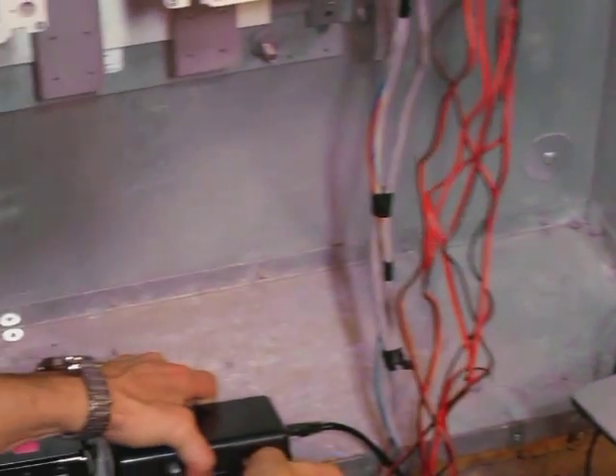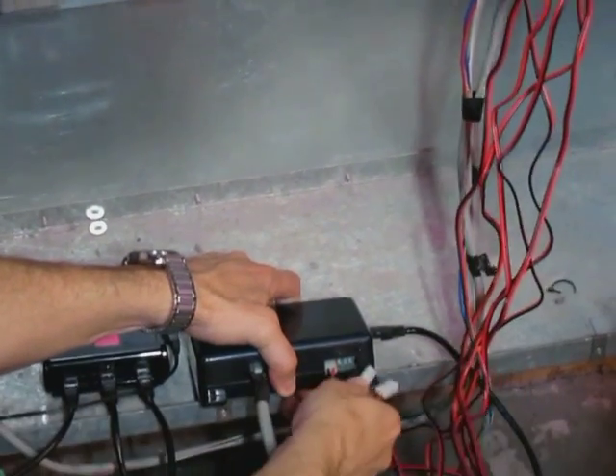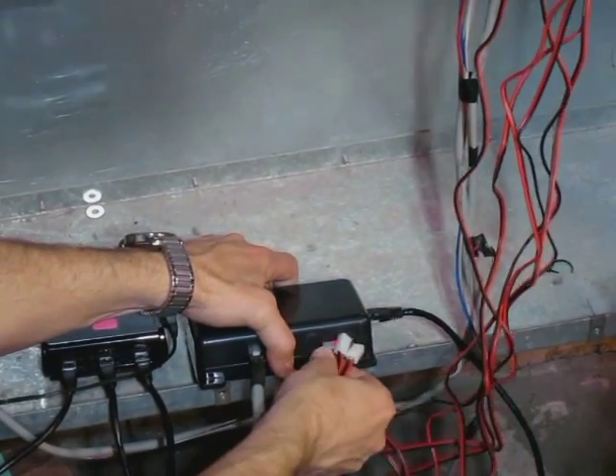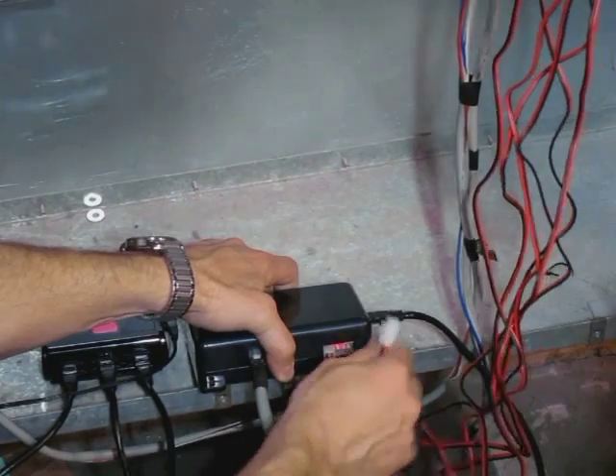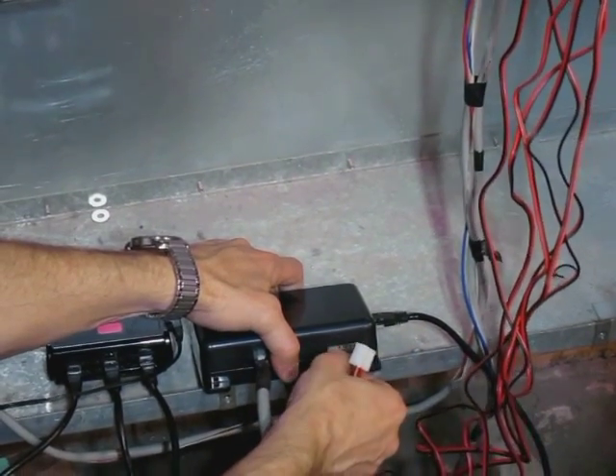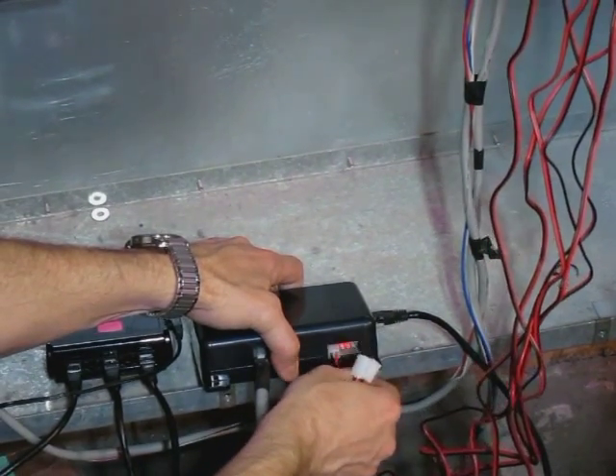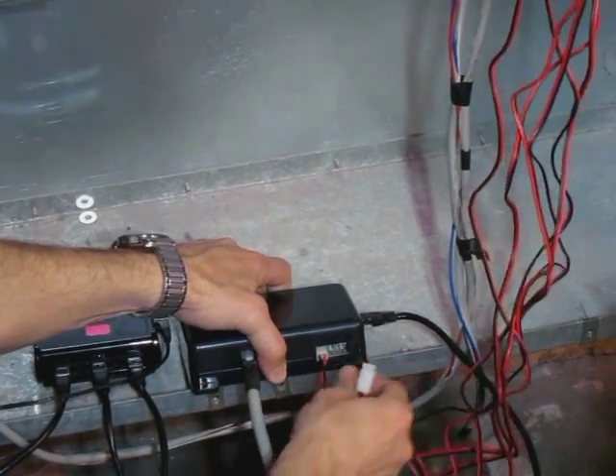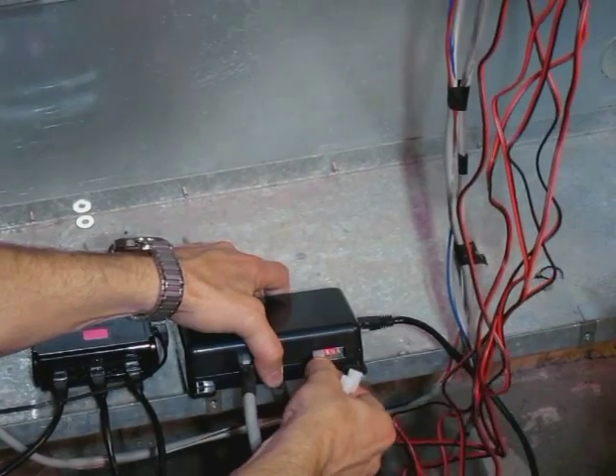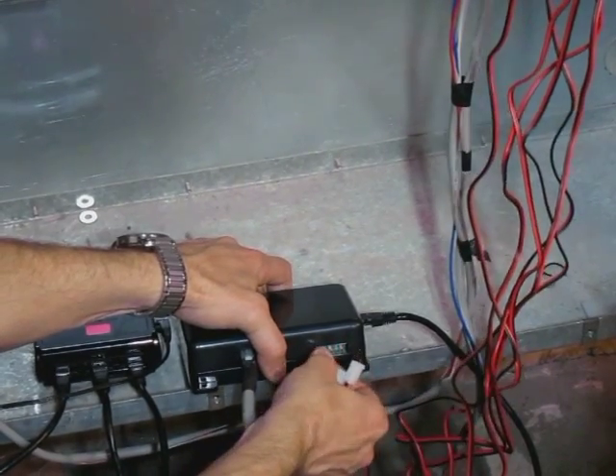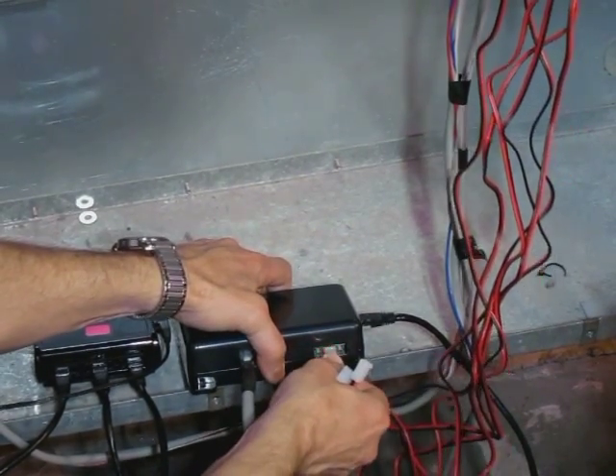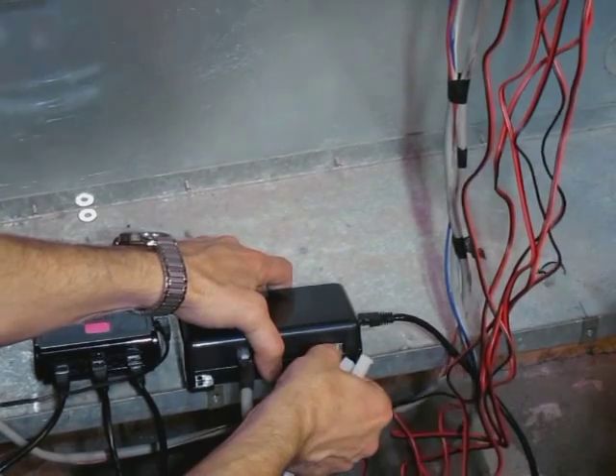I'm just going to unplug all three of these. And you can do this with the MTU under power because there's minimal current on these connectors from the CT. And I'm going to take the connector that's in the A phase and I'm just going to move it to the B phase and see what I see there now.